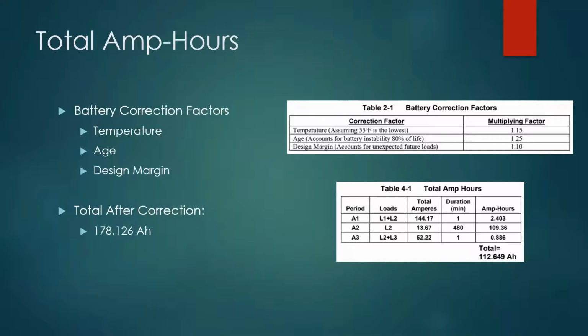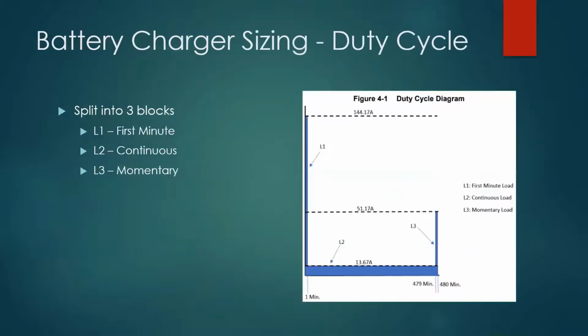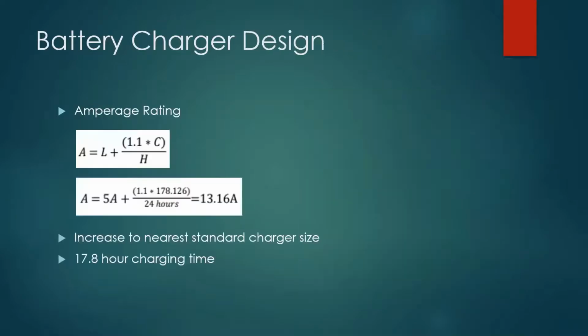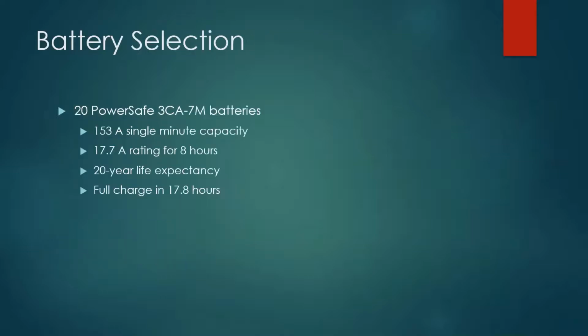The total amp hours of our loads were calculated using 3 battery correction factors of temperature, age, and design margin, which were 15, 25, and 10% respectively, giving us a total of 178.126 amp hours. Our battery charger sizing duty cycle was split into 3 different blocks of first minute, continuous, and momentary. We were able to use these calculations to find our amperage rating of 13.16 amps, which we increased to the 16 amp standard battery charger size. This gave us 17.8 hours of charging time. So we ended up deciding on 20 power safe batteries, which gave us 153 amps of single minute capacity, as well as 17.7 amps of continuous capacity. These batteries are expected to live for 20 years.